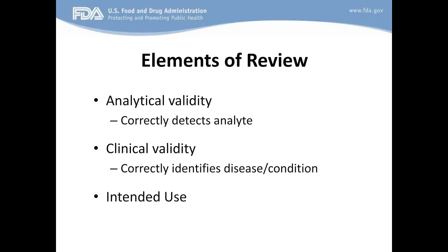So analytical performance, this is really fairly well established. There are several ways to do it. It's well established in the sense of theoretically what we should do. It is actually very dependent on the type of analyte, the type of test, and what are believed to be the important factors that have to be controlled. But typically, people look at accuracy. That is, how well does the value relate to truth? Is there any bias? Precision. That is, how repeatable is that answer? If you do it again and again, how much imprecision is there? Is the test specific? Are there other analytes, other things that may interfere with the accuracy of the test?